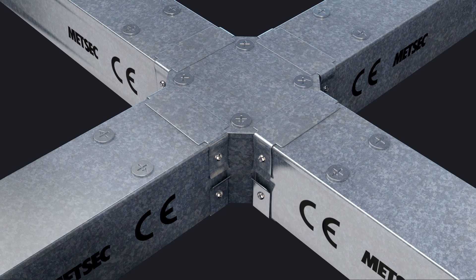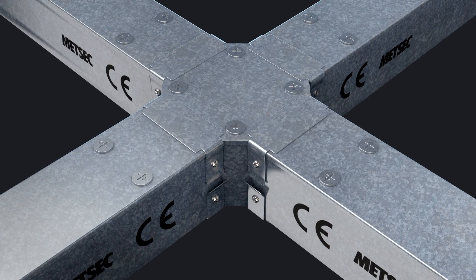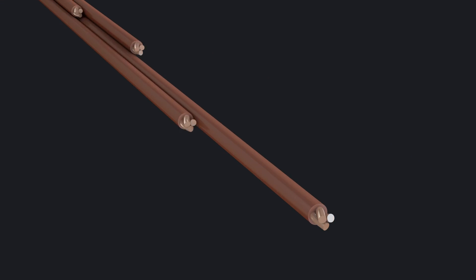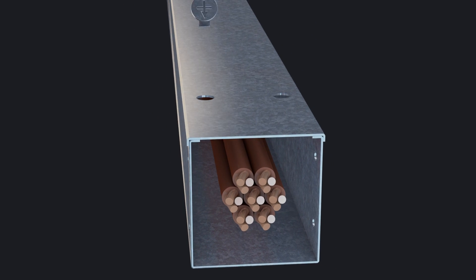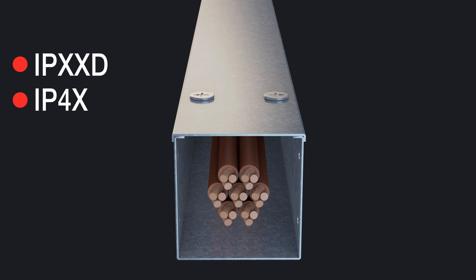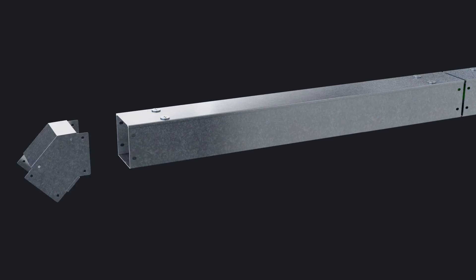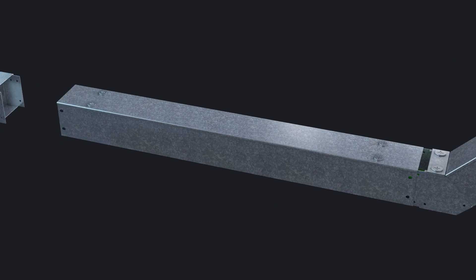This is to offer our customers full reassurance and compliance when it comes to responsible manufacture and procurement, all at the highest quality. Currently, British standards for metal cable containment systems demand that all single insulated non-sheathed cables be contained in an enclosure that meets either IP4X or IPXXD rating. These ratings provide a specific degree of mechanical protection from the ingress of solid objects to prevent the disturbance of contained unsheathed cables and potential short circuits.